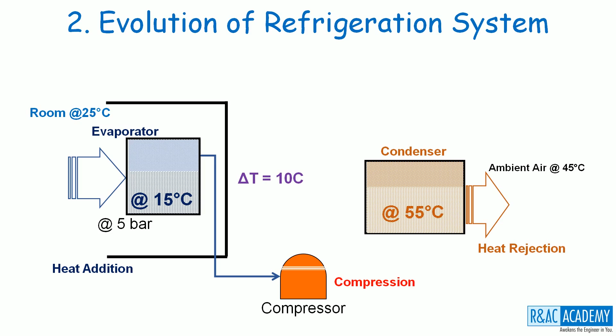The compressor then increases the pressure of the refrigerant vapor from 5 bar to 15 bar and delivers it into the condenser. What is the significance of this number 15 bar here? 15 bar is the saturation pressure corresponding to the condensing point of 55 degrees centigrade for R134A refrigerant. Therefore, as the condenser is maintained at 15 bar, the R134A vapor in it will condense at 55 degrees centigrade by rejecting heat to the surrounding medium, which is ambient air at 45 degrees centigrade. Hence, the refrigerant coming out of the condenser will be at 15 bar.